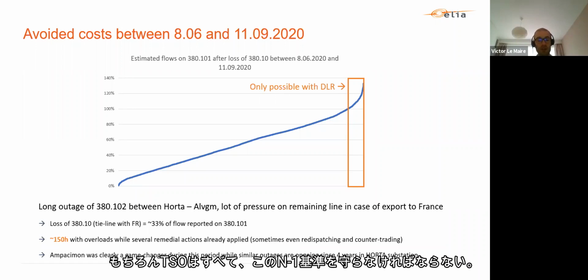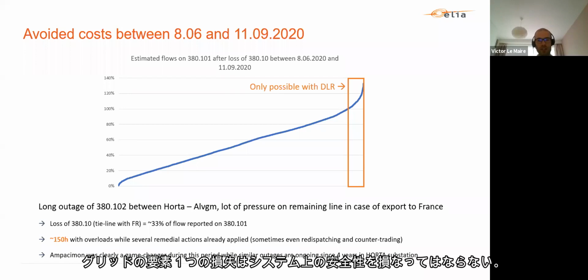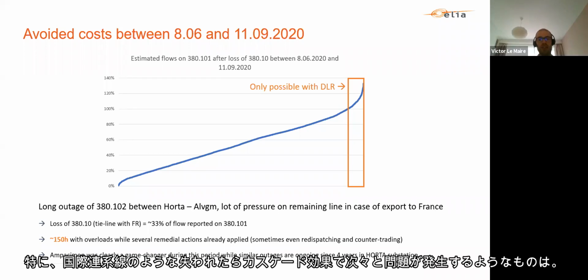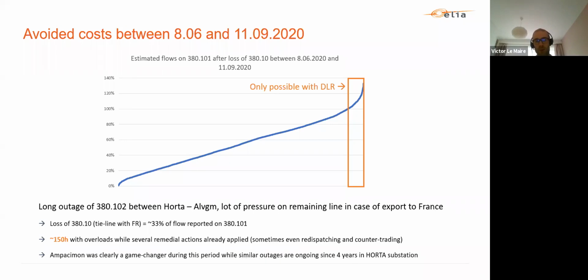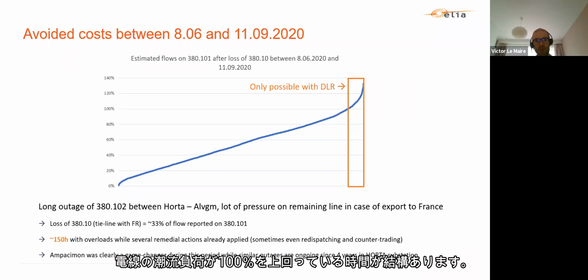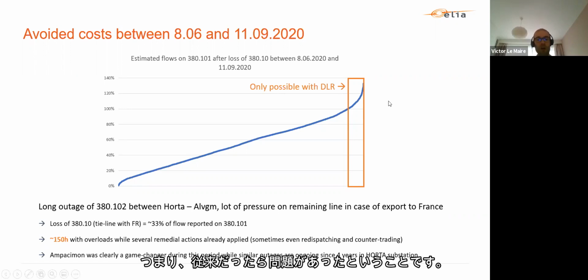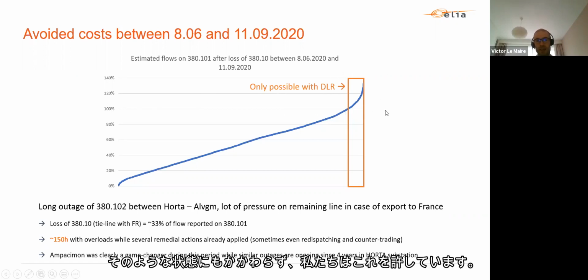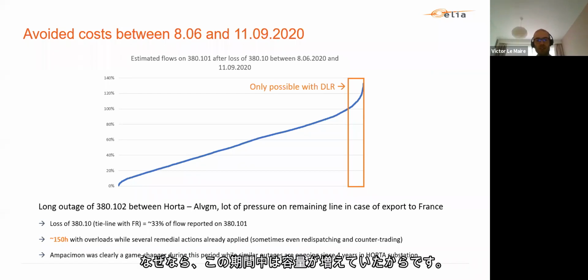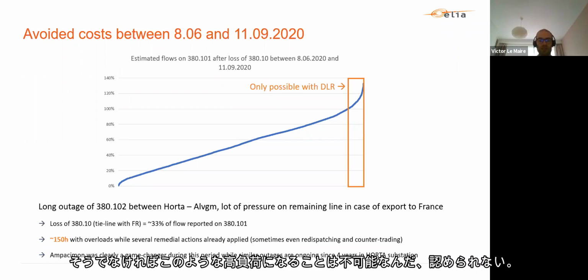All TSOs have to respect the N-1 criteria: the loss of any element should not create any problem on the grid, certainly on tie lines, where you could have a cascading effect and massive problems. Here we see in this graph that for a significant portion of the time, the load is above 100%, meaning you're above the static rating. Nonetheless, we've been through this and allowed it, which means that during this period we apparently had increased capacity.